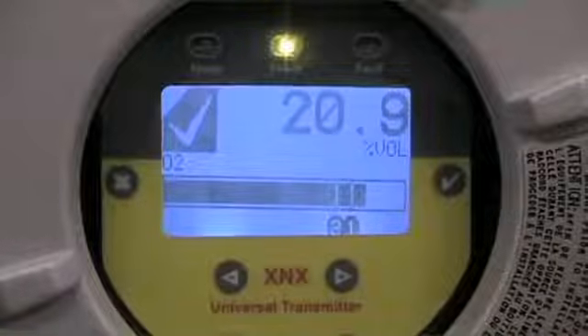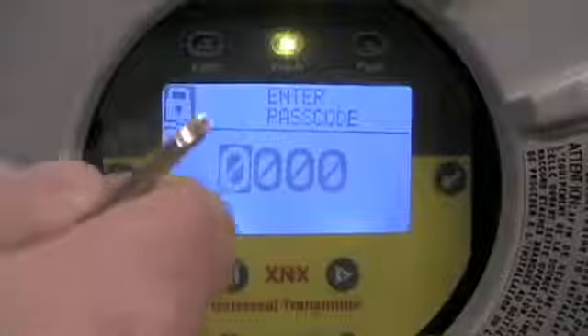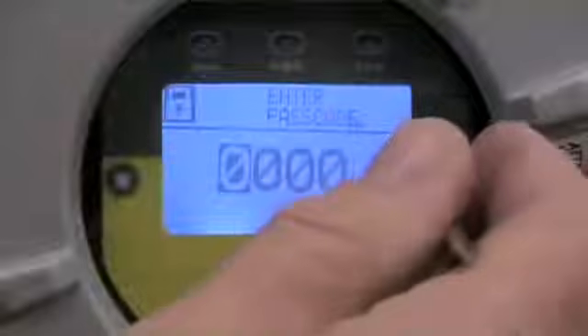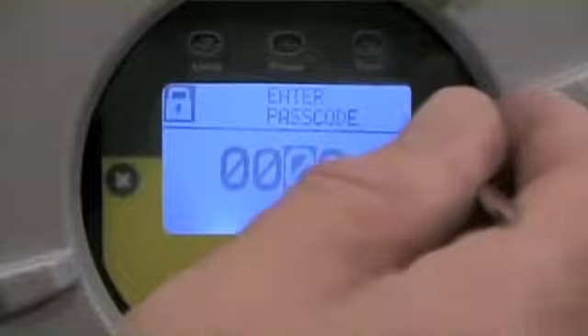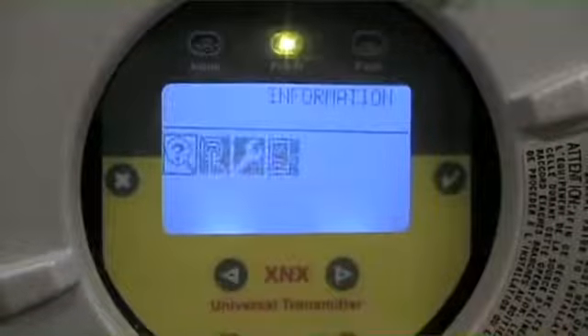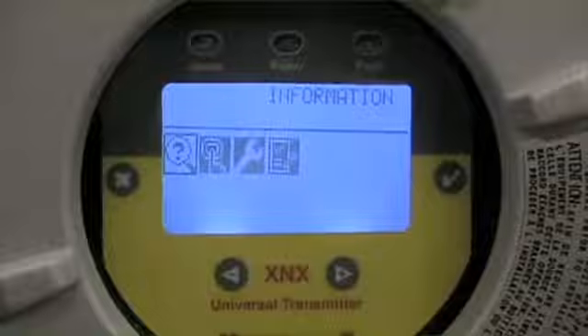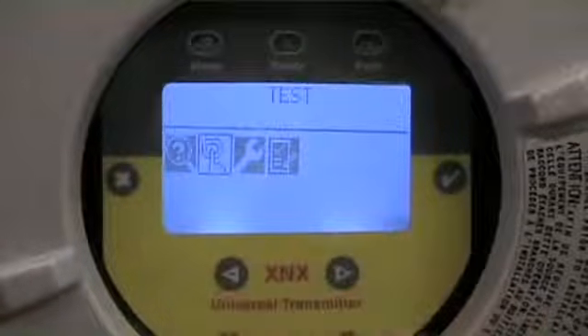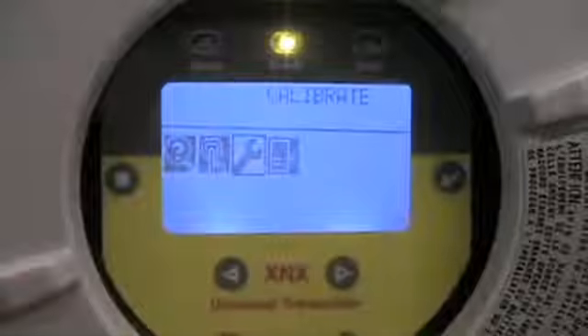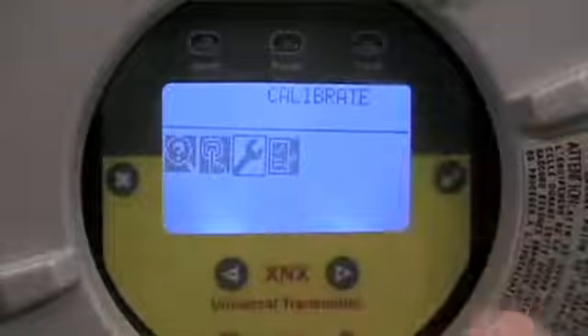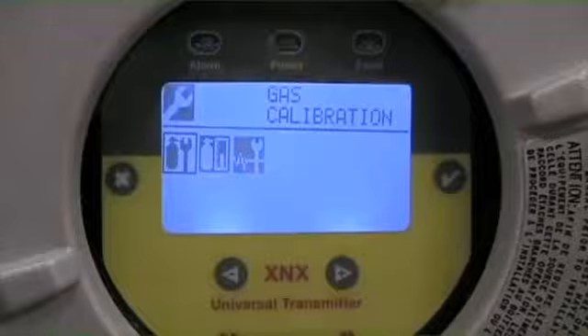In this segment, we'll focus on bump testing, calibrating, and setting the calibration due interval on the XNX transmitter. Again, calibration functions require a level 1 password, so I'm going to use the magnet and trip over into the passcode level. Default is 0000, so that arrow mark is going to index across until I can accept. I'm now in my main menu, and these functions are going to be relative to calibration, so I'm arrowing over from information past the test menu into our calibration mode. Check mark to accept that function, and now I'm in my calibration menu.